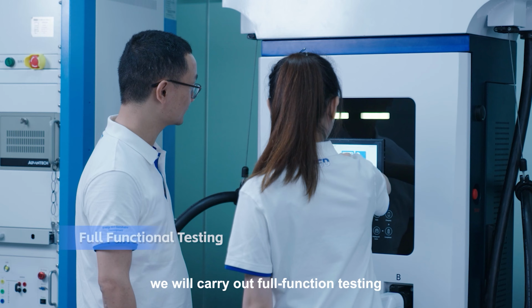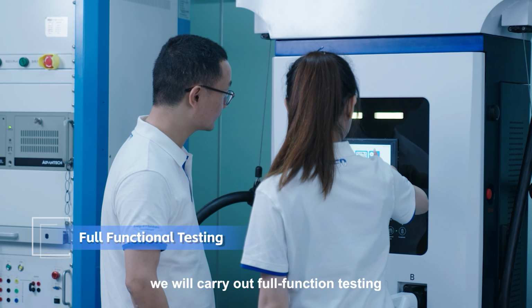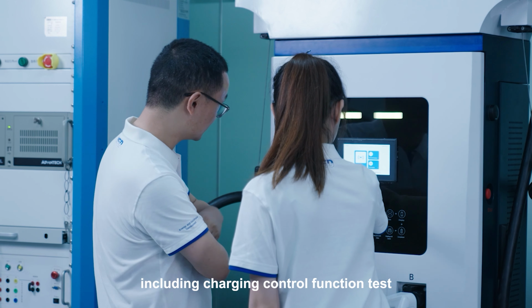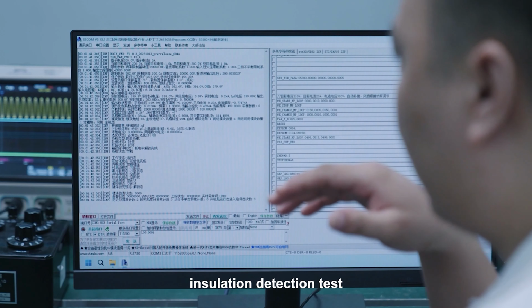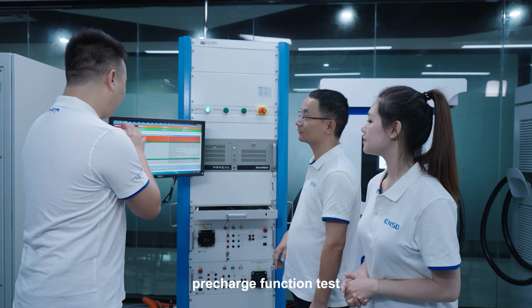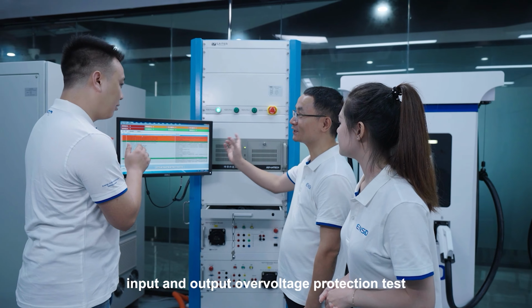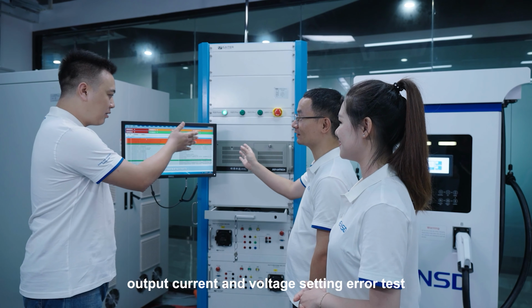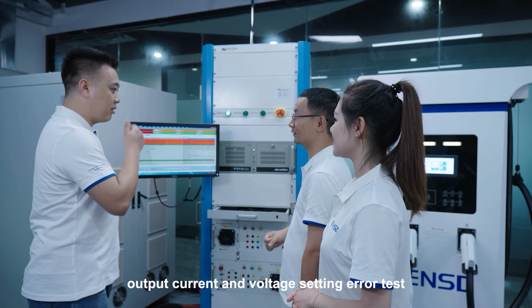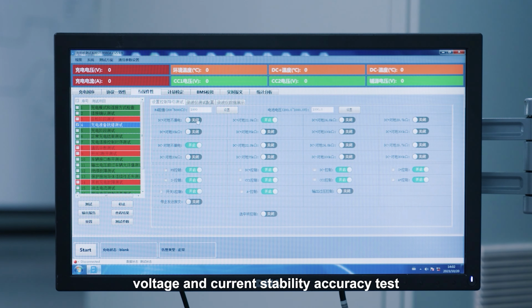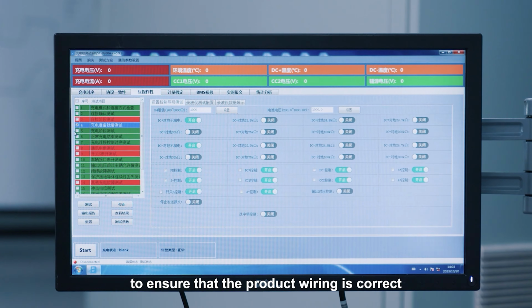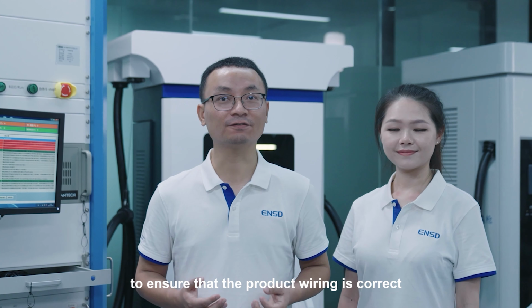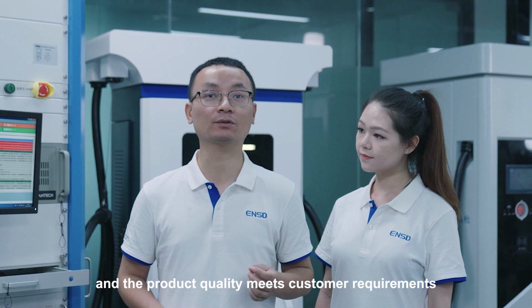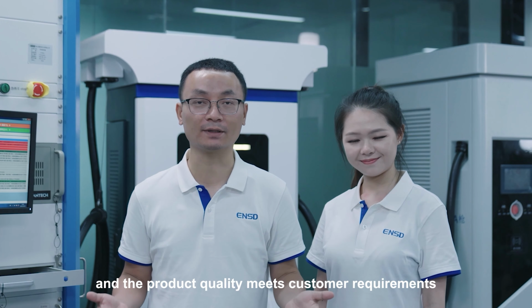Secondly, we carry out full function testing, including charging control function test, installation detection test, pre-charge function test, input and output overvoltage protection test, output current and voltage setting error test, and voltage and current stability accuracy test, to ensure correct wiring, perfect function, and product quality meeting customer requirements.